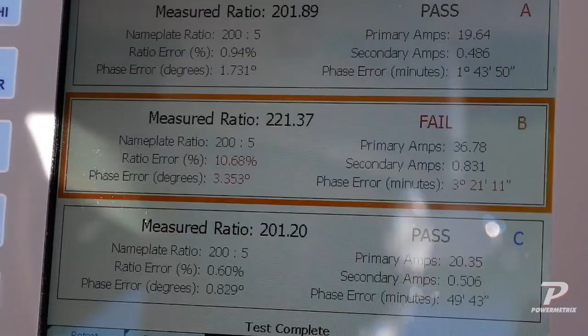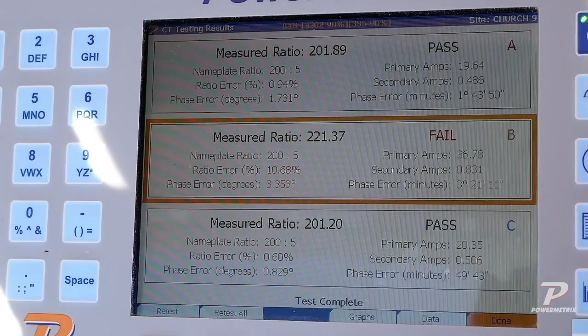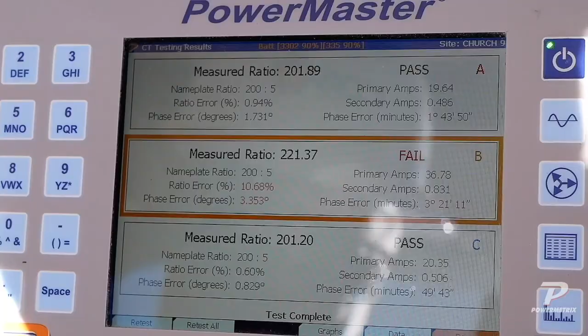So that's a good point. My load on B phase is 0.83 secondary amps on B phase, and I've got 36.7 primary amps. That should be enough for us to get a good test.